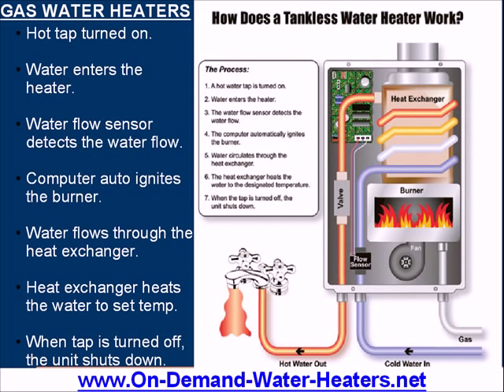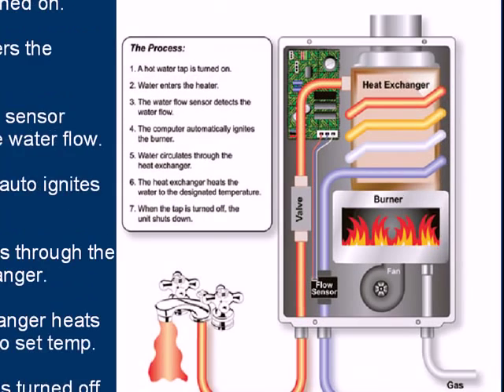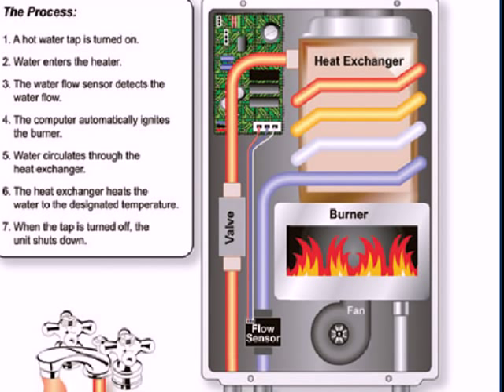So let's talk about the natural gas water heater for a moment. And how does it work? We have this picture here which helps to explain a little bit how it works. You'll see when you turn the hot tap on, there's water flow. Water comes in, you see the cold water in, there's a sensor there. As soon as you turn your hot tap on anywhere in the house, there's flow through into this water heater, and the water flow sensor detects that. As soon as it sees flow through the water heater, the computer there automatically ignites the gas burner, and it starts up and heats the water very quickly as it flows through the water heater, through the heat exchanger.